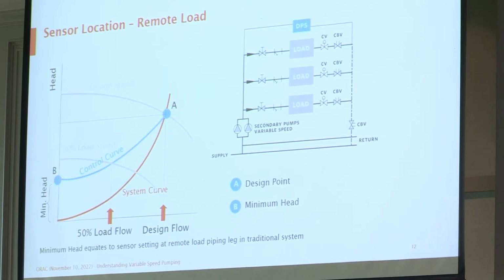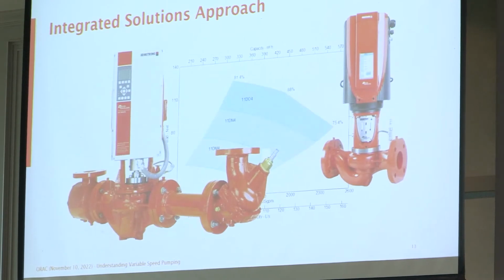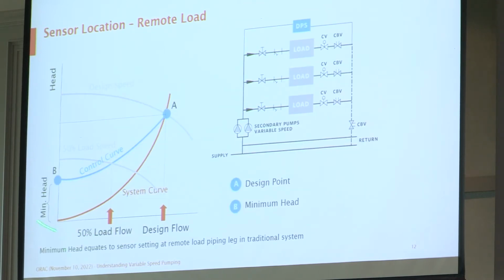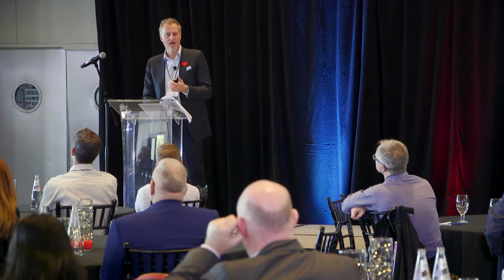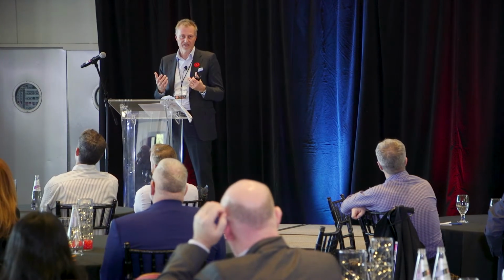When we have that DP sensor at the hydraulically most remote load, what that means is that all we need to do is have that minimum head pressure to get that volume of water to the sensor or the load, and then we have our control curve. And as a result, we're able to optimize the pumping solution, and we meet ASHRAE standards. Now, one of the challenges in this, first of all, is that once a DP sensor is located in the system, it's fixed. It's very difficult to move.